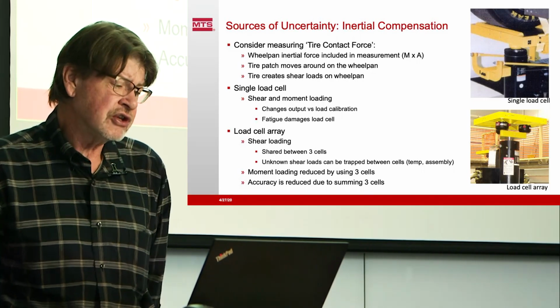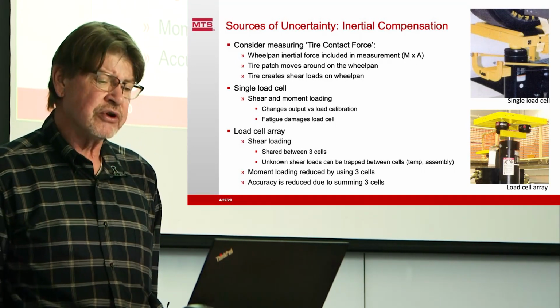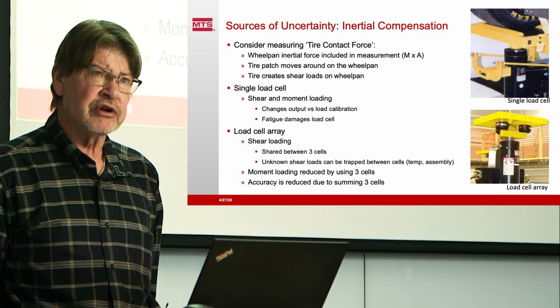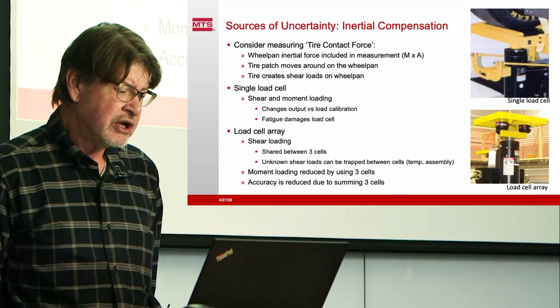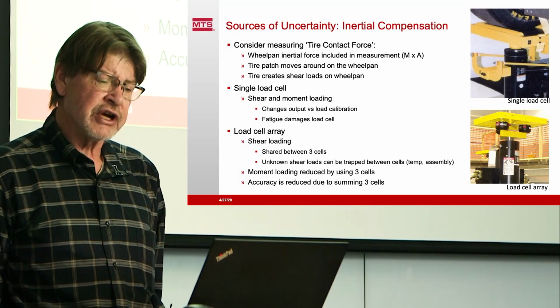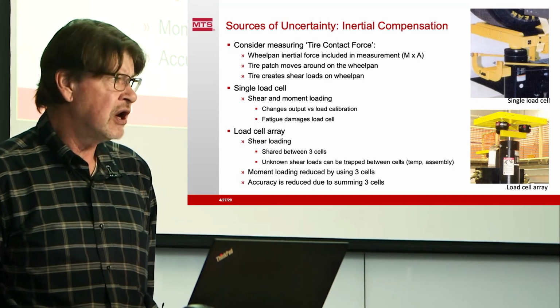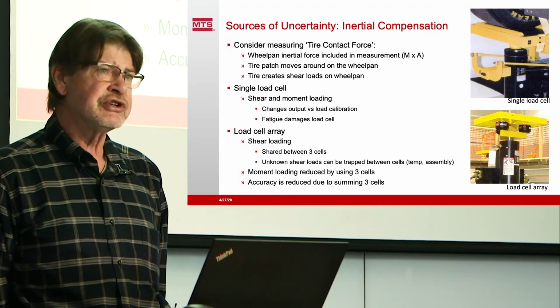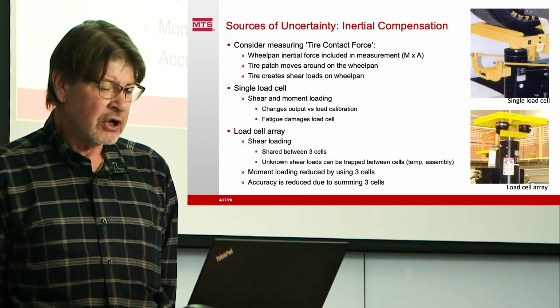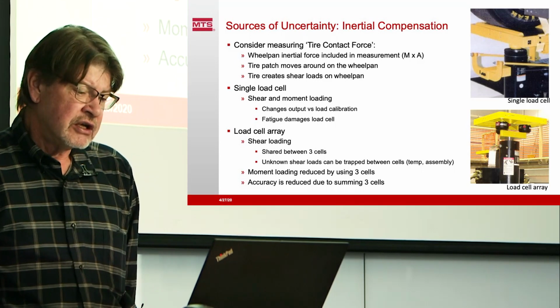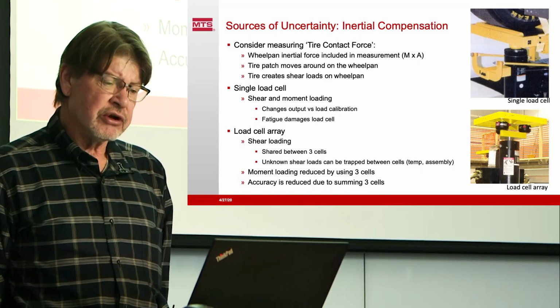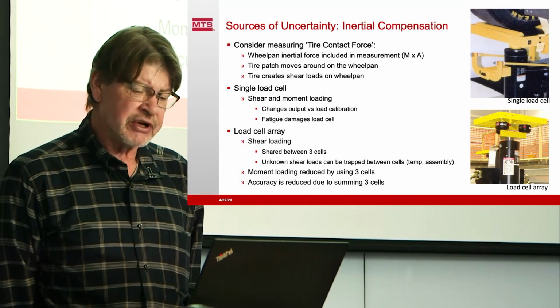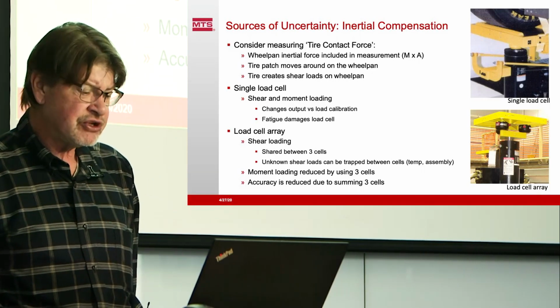With a single load cell, the shear and moment loading changes the output because we're eccentrically loading the cell, bending it and shearing it. And it fatigue damages the load cell. The tire can sit on one side and pound for a while, and we can repeatedly bend the load cell and cause fatigue damage. A load cell array, on the other hand, can share the shear loading from the tire between three cells, but it can have unknown loads trapped in between the three cells.